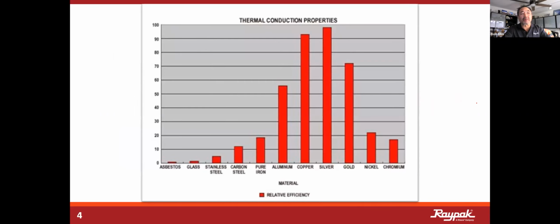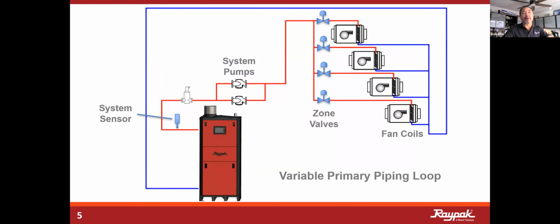First thing first, bear in mind that when you're talking about the heat transfer coefficients or the thermal conduction properties of the materials that the equipment is made of, you notice that by far and away the best, as far as commonly used in boilers or hot water, the best heat transfer material is copper. But as we get into high efficiency equipment, copper isn't going to manage the condensate. That is where we see a lot of stainless steel coming into play. But if you'll notice in the thermal conduction properties, it has the lowest heat transfer capability, so you have to use more of it. It's also going to stress more if you put too much heat into it. So that gives you a little bit of background there.